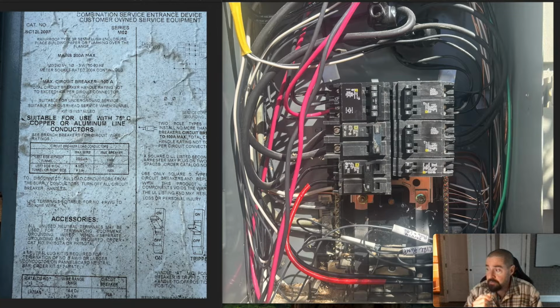Each one of those circuit breakers is considered to be a service disconnect. So you can have up to 6 service disconnects in a hot bus panel by code. You'll see in this panel, you've got a bunch of single pole breakers and quadplex breakers. So this is a code violation. It would not pass inspection, and that's because it has over 6 service disconnects in this panel. Essentially, you have to be able to de-energize the entire service with no more than 6 throws of a handle per the National Electric Code.